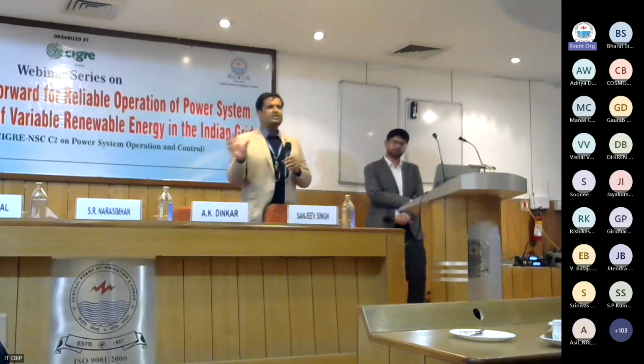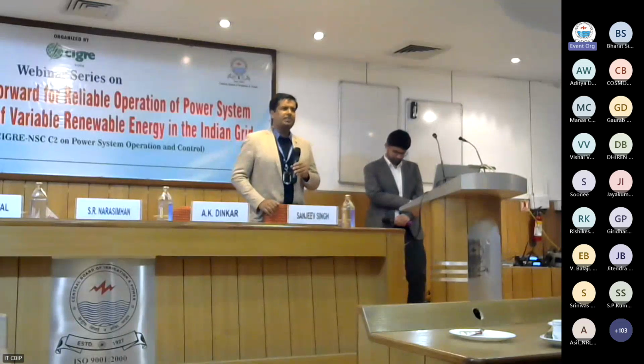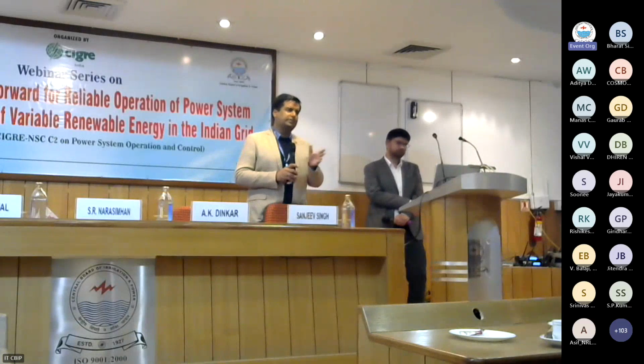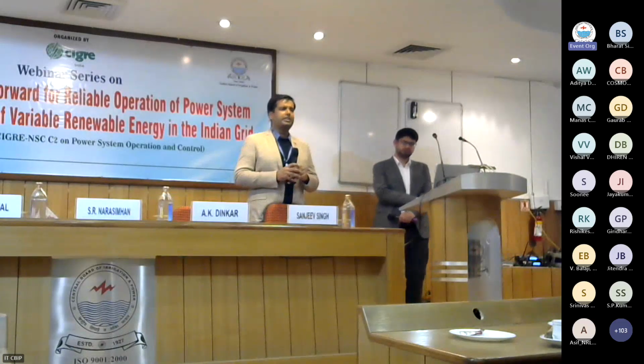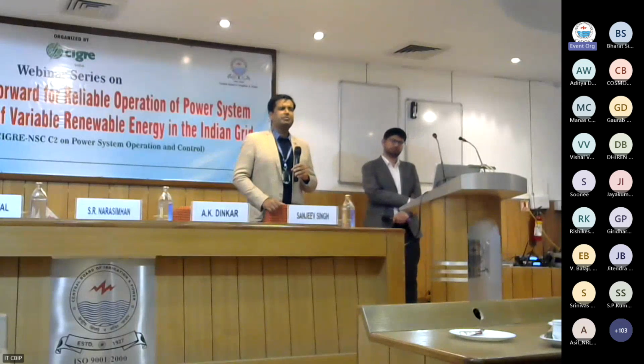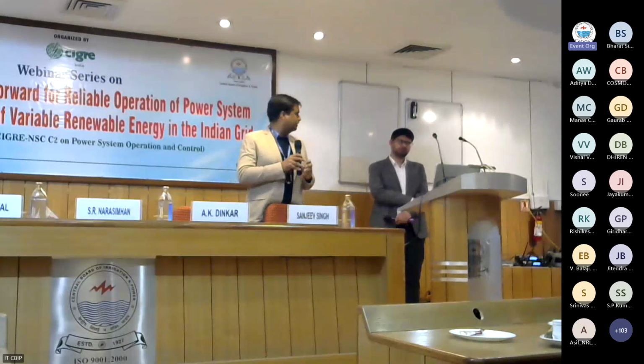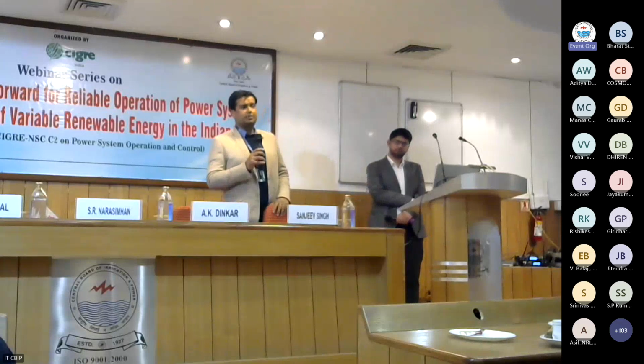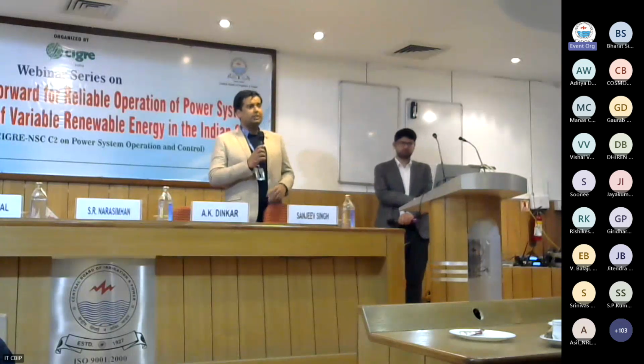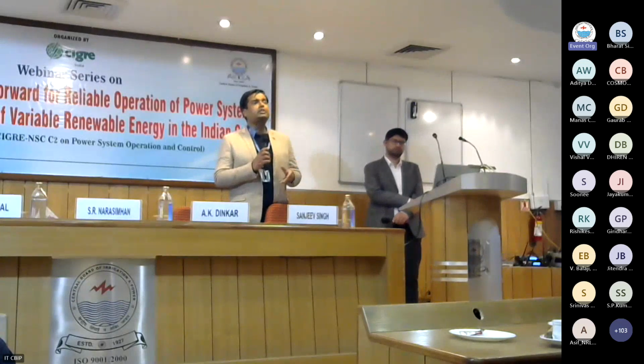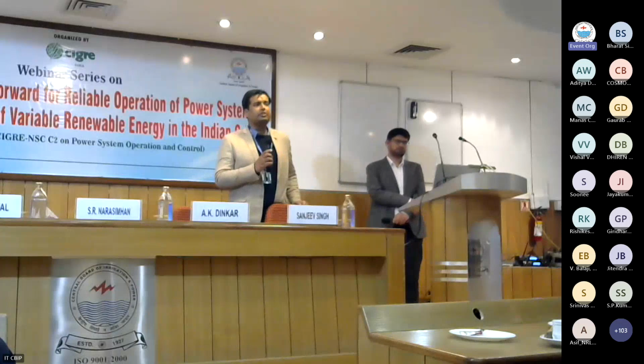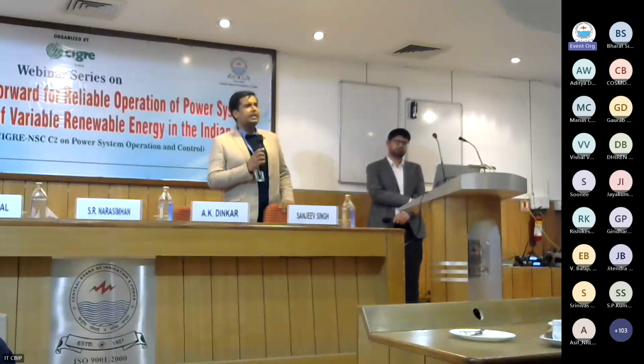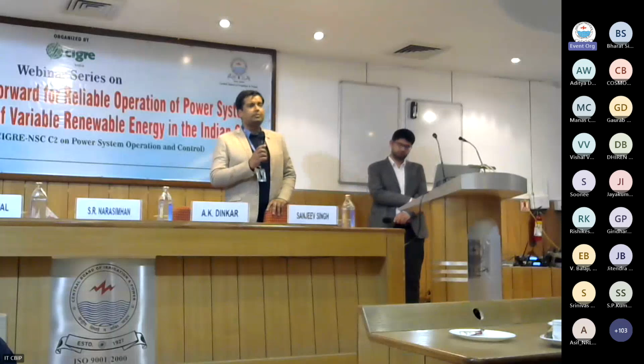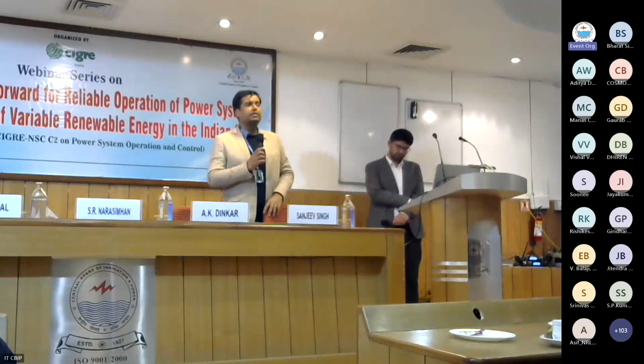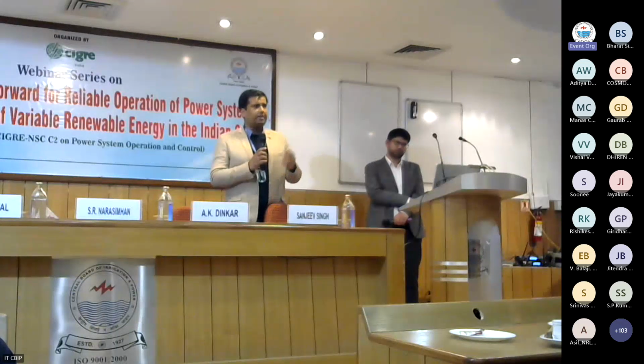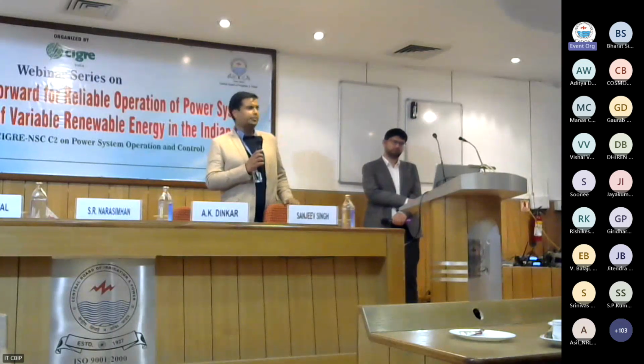So in 7 days, all these aspects can be monitored, the grid will see those things, what you are mentioning, that during low generation periods. So a 7 days period is quite comprehensive, and we assume that those are covered. Other than that, during the pre-commissioning stage, as a requirement of first-time charging, we are also identifying and validating the plant models in the frequency domain for the harmonics. In the PSCAD and EMT models, all the available EMT models, we are using that to identify the possible harmonics and the power quality of the plants.